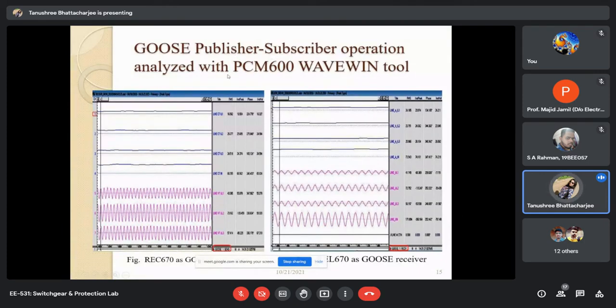In PCM 600 we built the whole project, then we ran the project and got these outputs. You can see there is a GOOSE send message from one relay, the REC relay, and this is the REL relay which received the GOOSE within 4 milliseconds. We actually got the timing within 2 milliseconds.